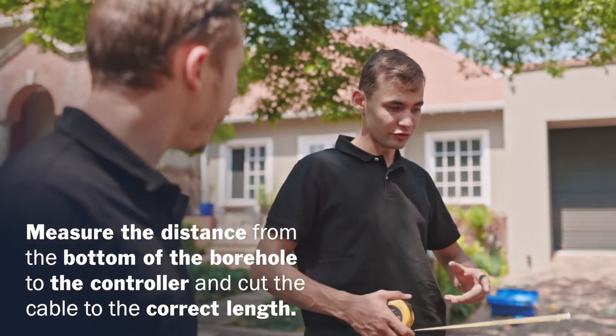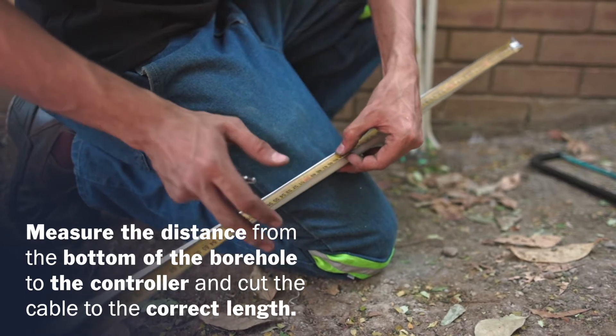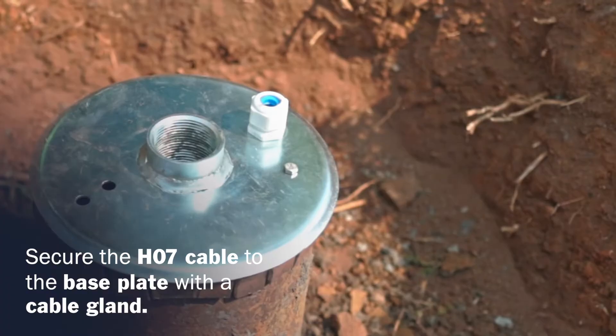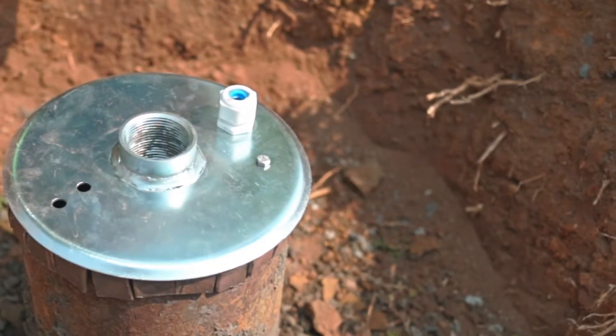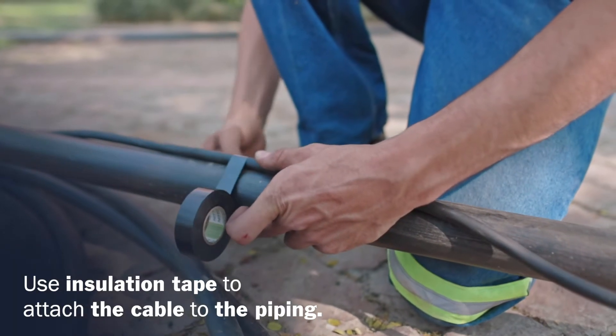Measure the distance to the borehole controller. Add the pump's depth and cut the pump's power cable to the correct length. Secure the H07 cable to the borehole base plate with the correct size compression cable gland for protection. Secure the H07 cable to the piping using electrical installation tape.